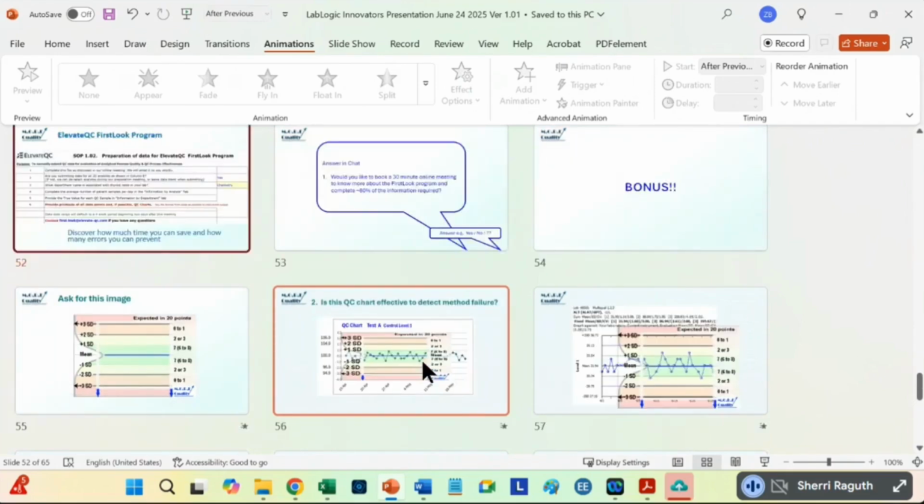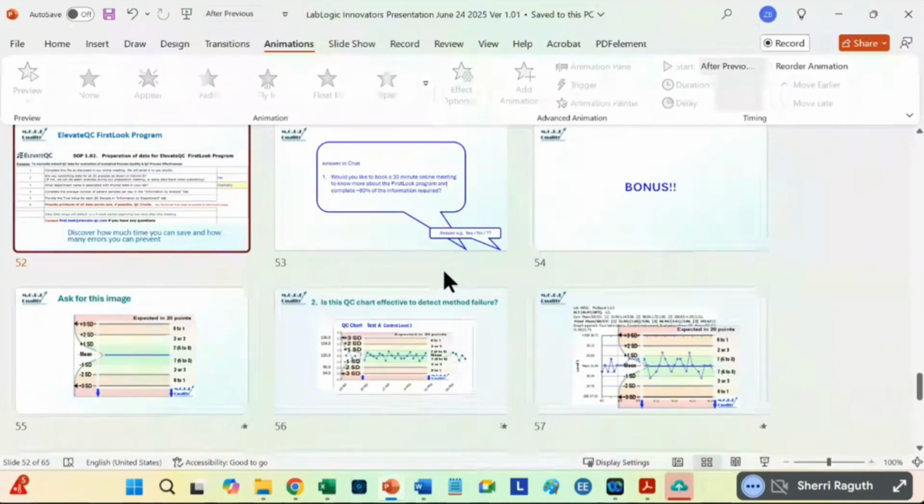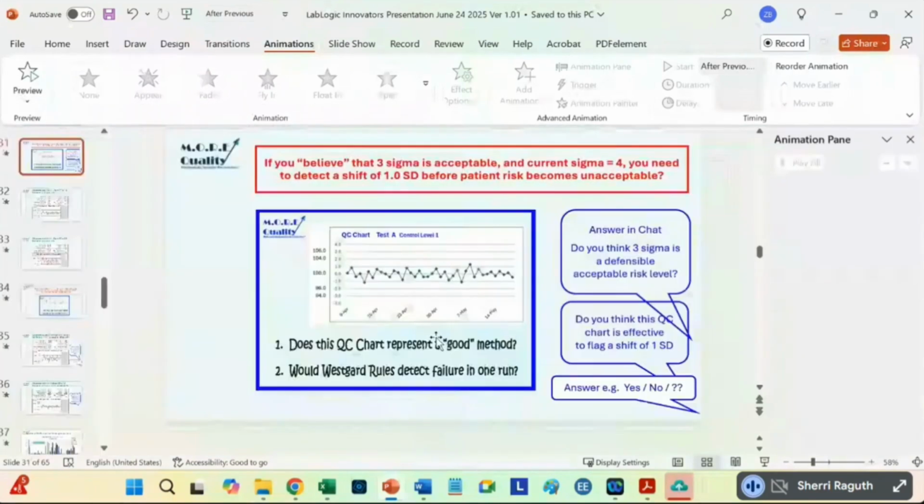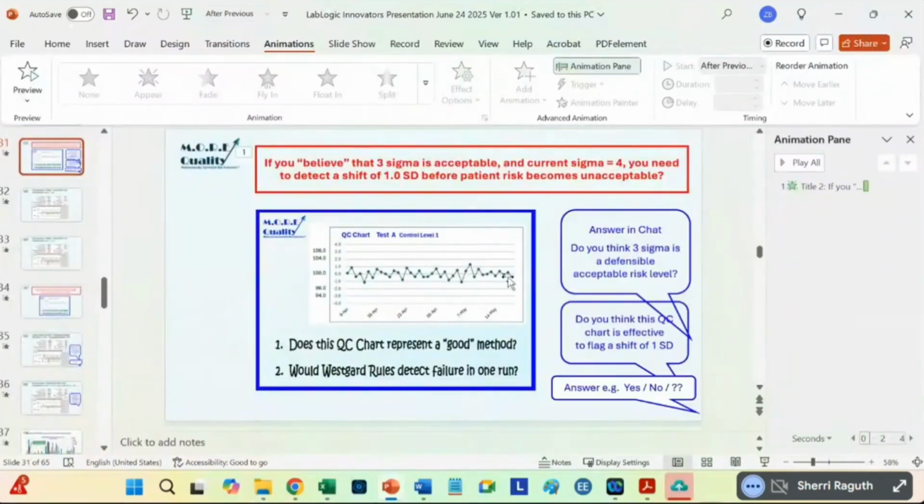Asan wants to know, what's the best way to establish lab mean and SD from manufacturer mean and SD? You measure it. You take your data points and calculate it. Like here, you would take all the individual data points in here, and are you doing your software on a computer of some sort? I would take it, or in Excel even.